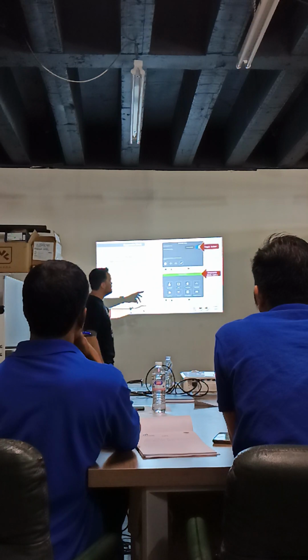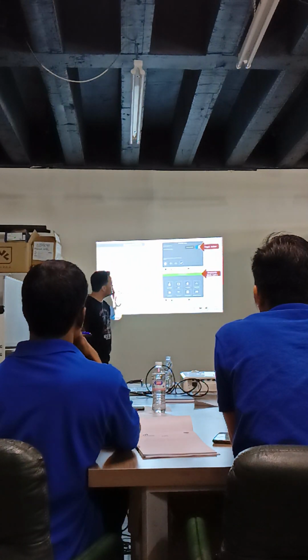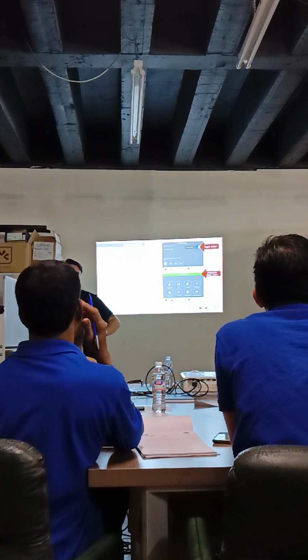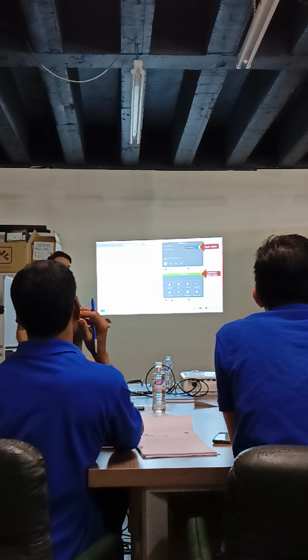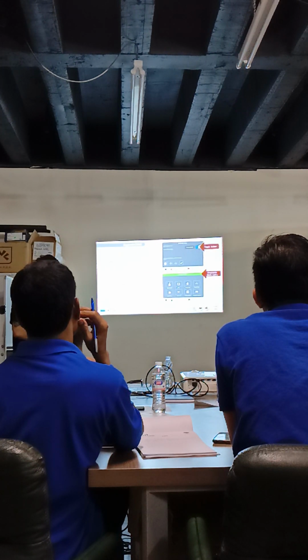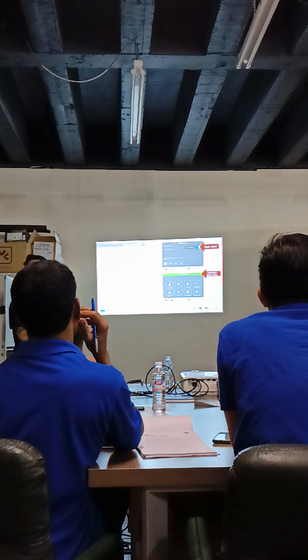The other one I love is the heater - is it heater state or is it relays? No, I think it's heater state. This lets you switch on the heaters separately. So if you have a problem with heating and you don't know if it's the thermocouple, the contactor, the solid state relay, or a problem with power...